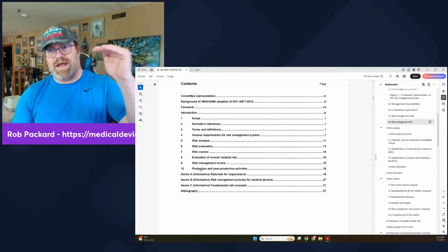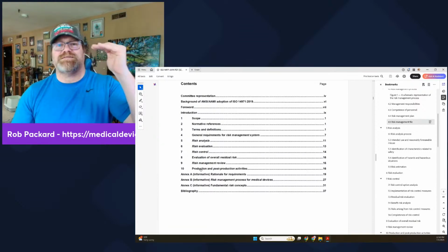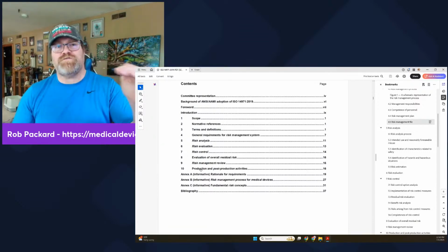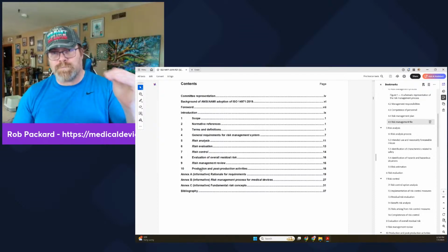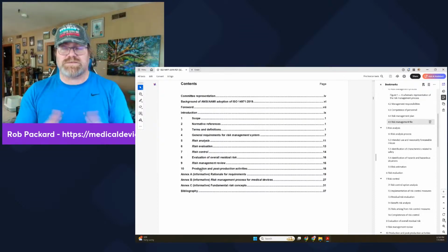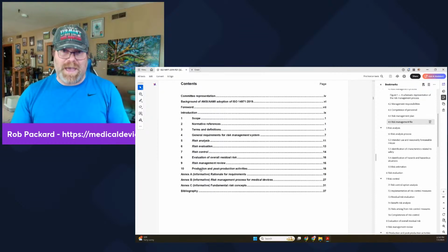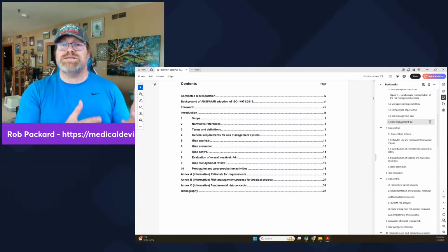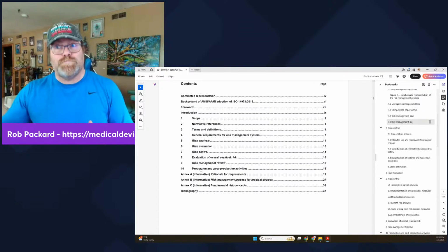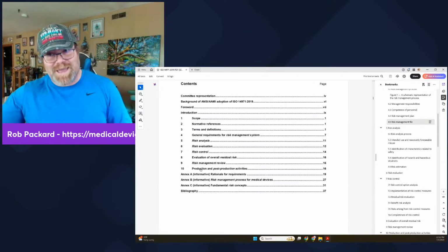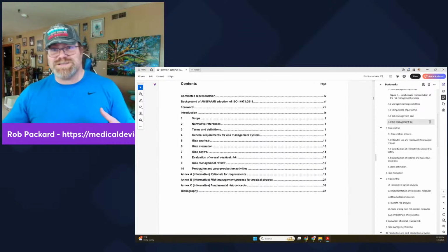You start with death. If it's a 5, it's death. If it's a 4, there's a serious permanent injury, like paralysis, for example. You're not dead, but you're paralyzed, very bad. A 3 is a serious injury that requires medical attention, or really bad things will happen, like death, like infection, things like that.